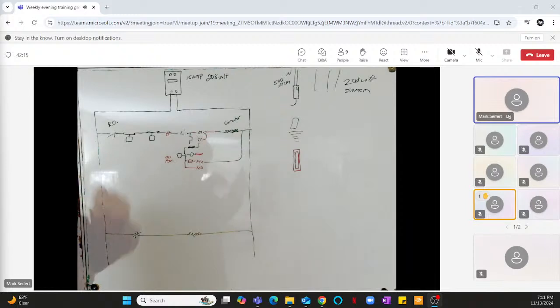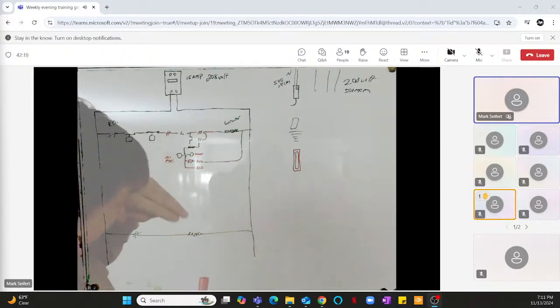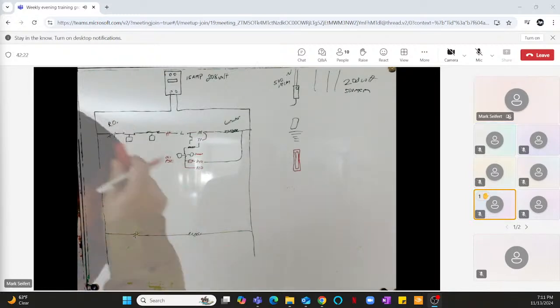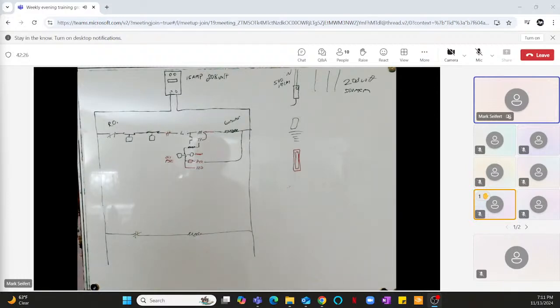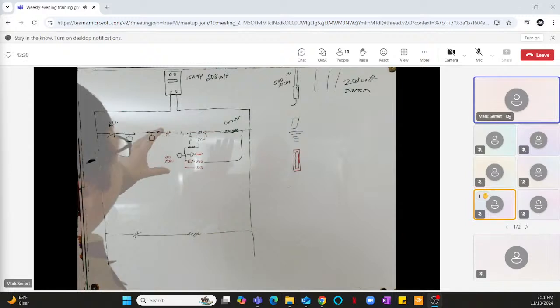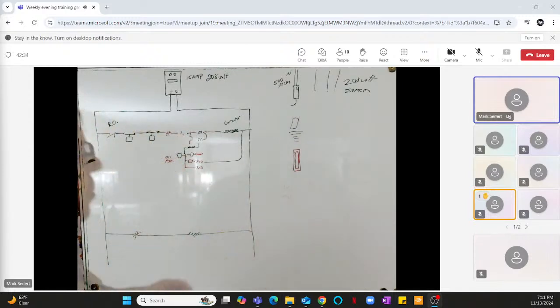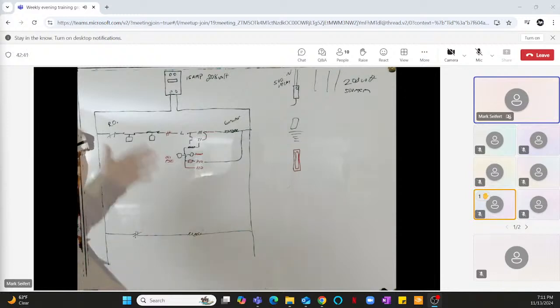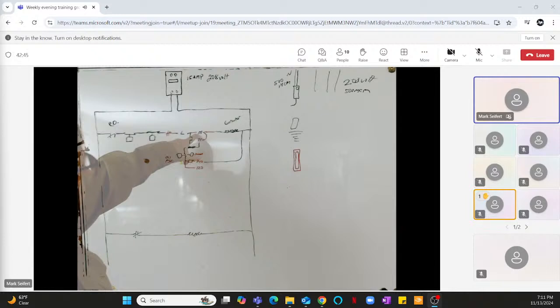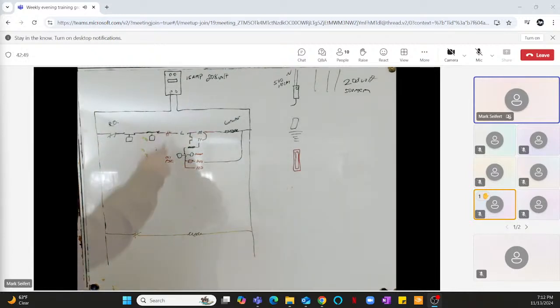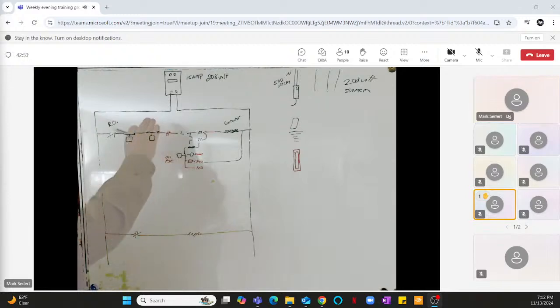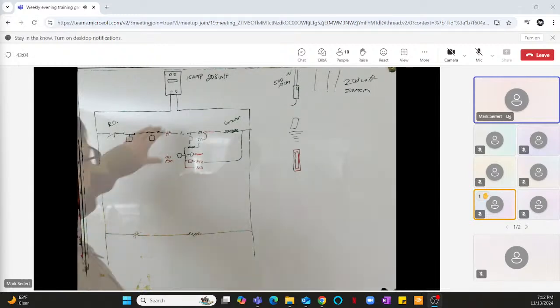There are some exceptions when you come to demand cooling, especially retrofitted in. We could go over that. Maybe we'll save that for the next one, because there's a couple of ways to do demand cooling. The reason is that you don't want that solenoid, let's just say, if it trips on oil fail, you don't want the solenoid to be energized. So let's just say I put demand cooling over here, and it's hot enough. Obviously, the compressor's not pulling in. It's probably not going to be hot enough for the solenoid to come on. But let's just say it's a super hot day. There is a chance that the solenoid could come on, the way it's wired, before this.